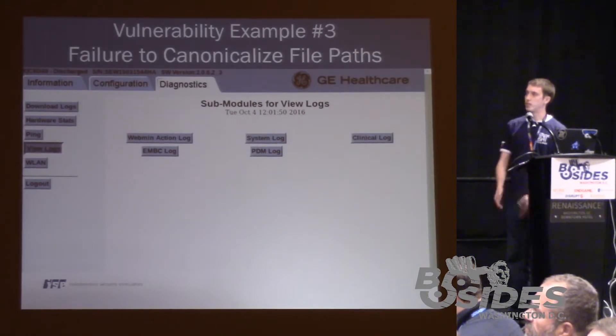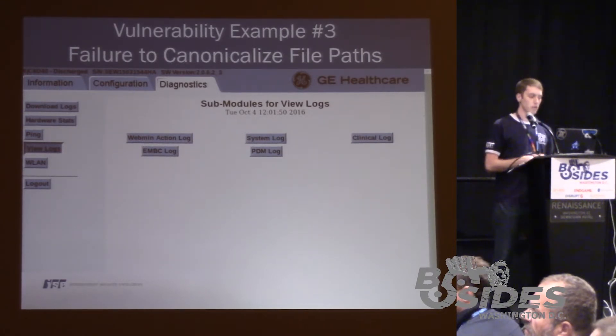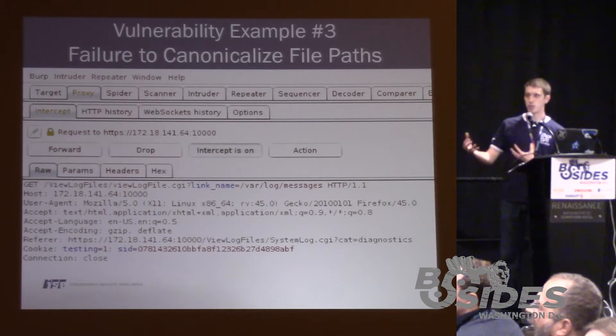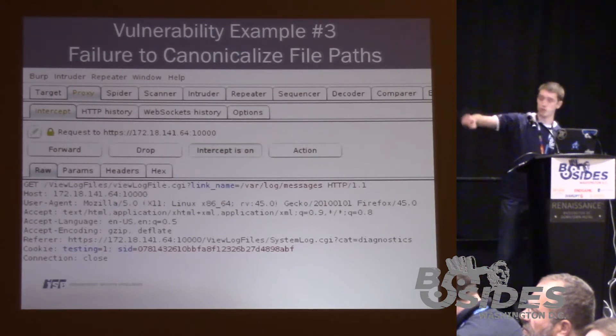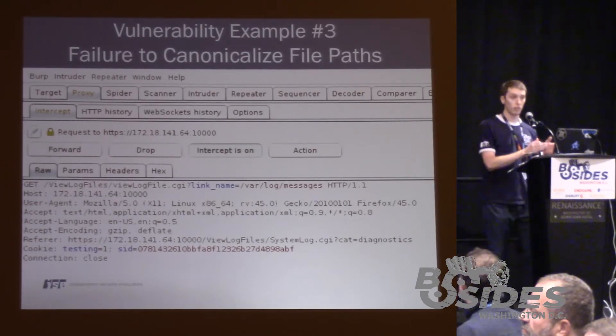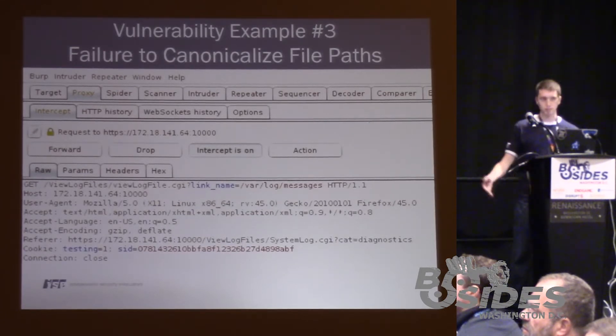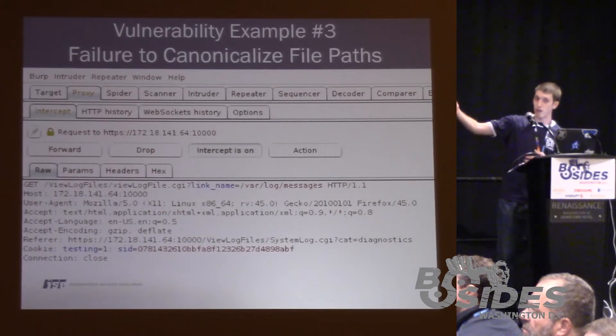Here we're showing the GE CareScape. While playing around with this device, we noticed there was some functionality to view log files. When we clicked on a view logs button, the device issues an API request — a GET request to the viewlogfile.cgi file — with an HTTP parameter called 'link_name'. The value of link_name looks awfully similar to a file path, and sure enough, /var/log/messages is a file that exists on a Linux system. If you request this file, you get the messages file.